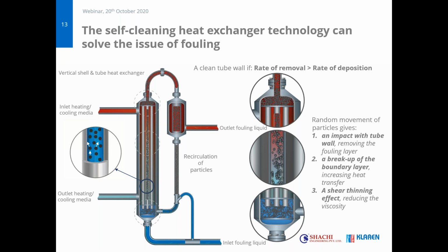But we have the same heat transfer coefficient with these low velocities because of the benefit of the cleaning particles, because the cleaning particles increase heat transfer. They increase heat transfer with a factor of 3 to 4 if you would compare it with the same velocities. If you compare a conventional design heat exchanger in clean conditions with our system, the heat transfer would be comparable. Of course, with the main benefit that because of the cleaning, our heat transfer coefficient remains the same.